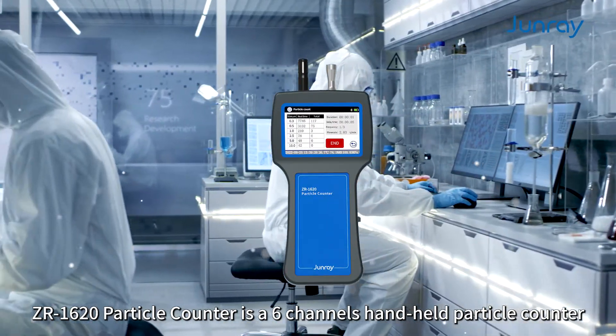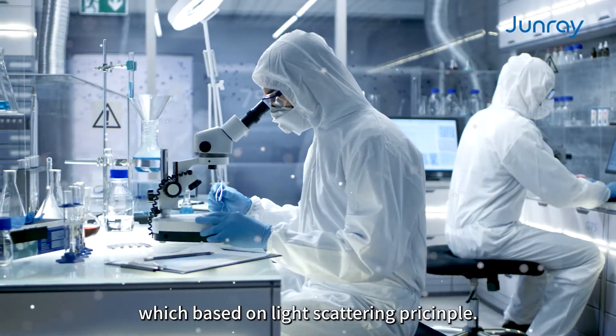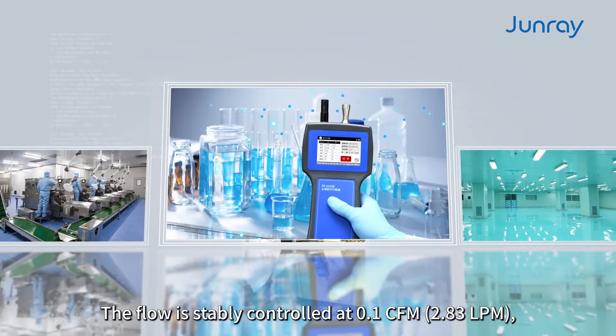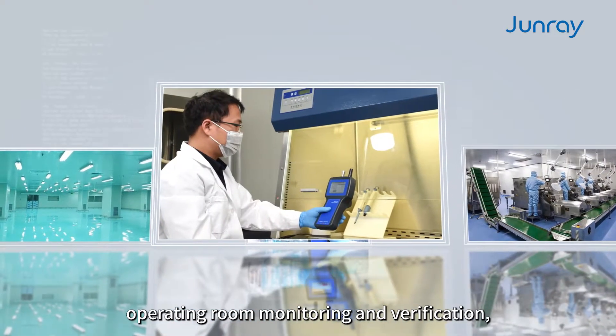The ZR1620 Particle Counter is a six-channel handheld particle counter that counts particles from 0.1 microns to 10.0 microns, based on the light scattering principle. The flow is stably controlled at 0.1 CFM, 2.83 LPM.